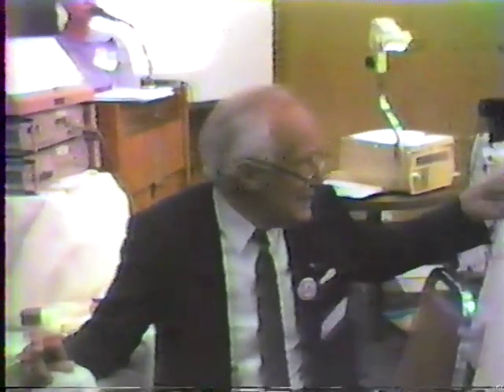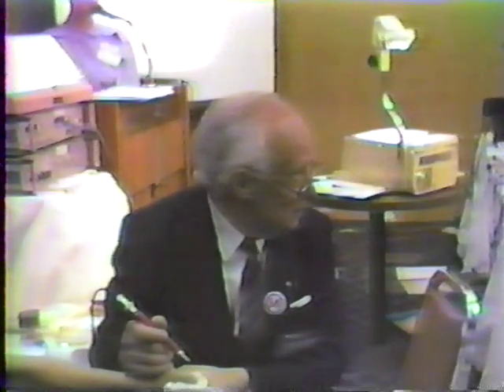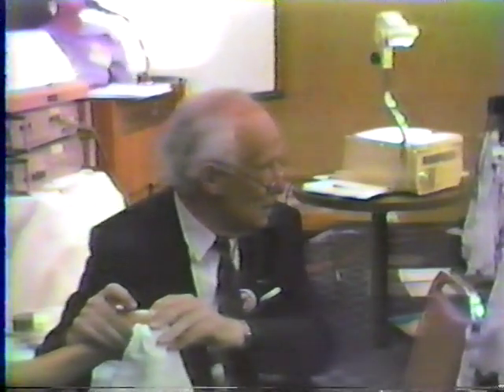But if with every point you want to test the whole indicator drop, sometimes you have to wait for a period of about 40 seconds, pressing one point for 40 seconds, to see how far it will drop. That is a strong stress to the point, so that you can no more do the other testing afterwards.